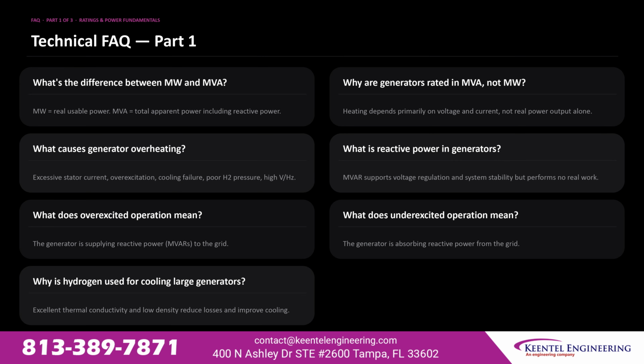What's the difference between megawatts and megavolt amperes? Megawatts is real usable power. Megavolt amperes is total apparent power including reactive power. Why are generators rated in megavolt amperes, not megawatts? Heating depends primarily on voltage and current, not real power output alone. What causes generator overheating? Excessive stator current, overexcitation, cooling failure, poor hydrogen pressure, and high volts-per-Hertz operation. What is reactive power in generators? MVAR supports voltage regulation and system stability but performs no real work.